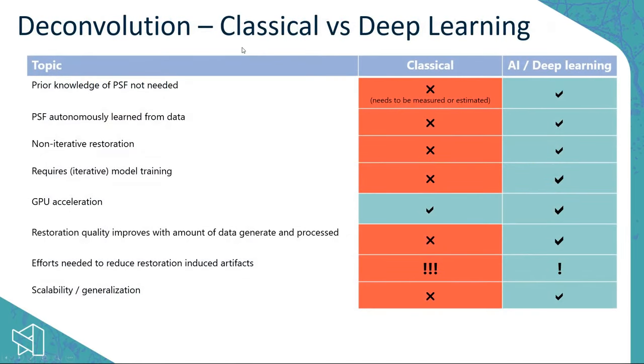Now, what I'm particularly interested in discussing is how the classical approach compares versus the AI or deep learning approach to image deconvolution. Looking at the first item: prior knowledge of the PSF is not required for deep learning, whereas for classical deconvolution the PSF is typically required. It either needs to be measured — which is very time-consuming, requiring bead measurements in multiple conditions — or estimated based on hardware knowledge.